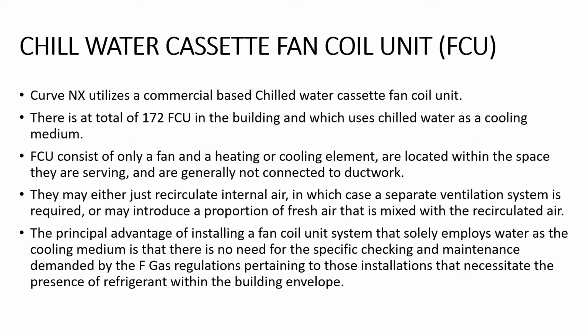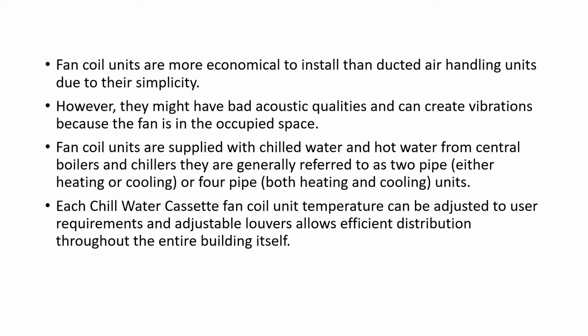So the principal advantage of installing a fan coil unit system that solely employs water as the cooling medium is that there is no need for the specific checking and maintenance demanded by the F-gas regulations pertaining to those installations that necessitate the presence of refrigerant within the building envelope. So fan coil units are more economical to install than ducted air handling units due to their simplicity. So basically the FCU is more simple. However, they might have bad acoustic qualities and can create vibrations because the fan is in the occupied space.